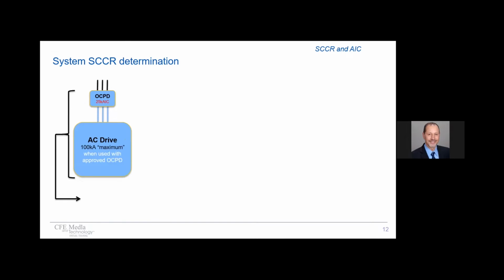Let's take a look at some examples. In this example here, we have a drive that's published with a maximum capability of 100,000 amps when used with a protective device. But in this case, the protective device that's being used on the input has an interrupting capacity of only 25,000 amps. So in the end, we have a withstand or SCCR capability of only 25,000 amps. So it's the lesser of the two.